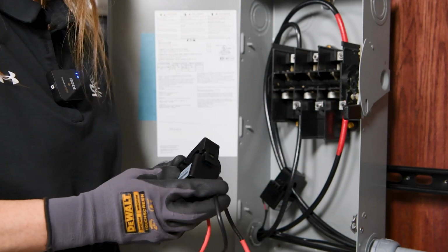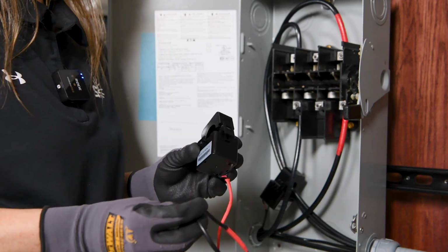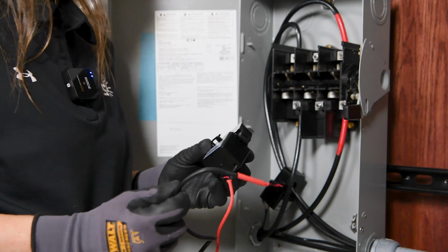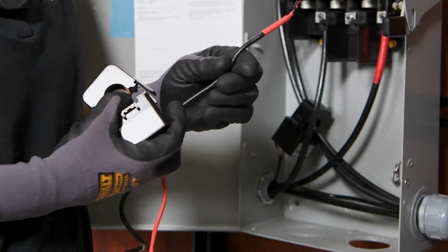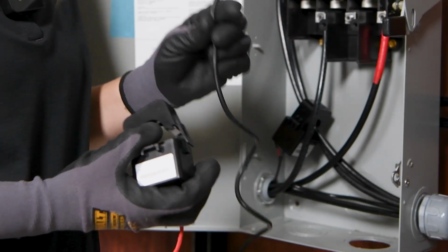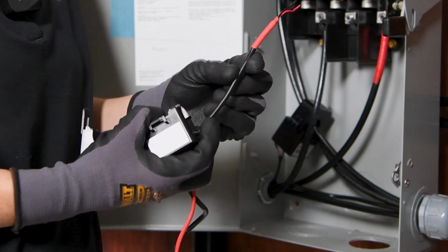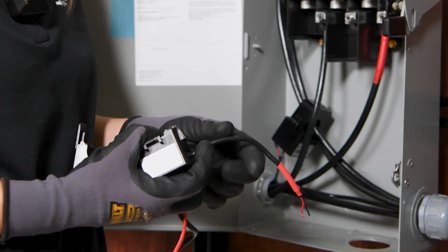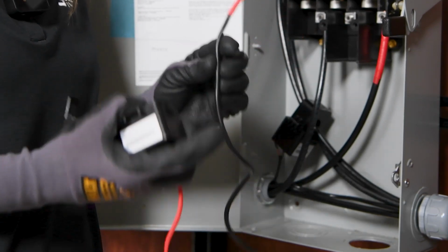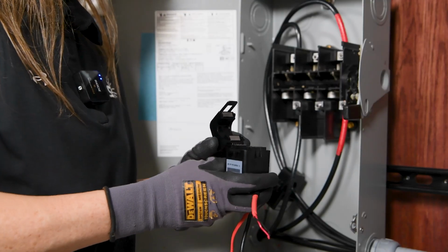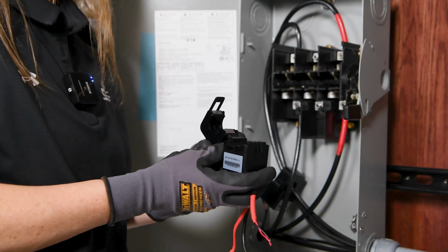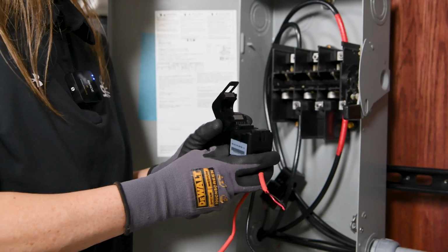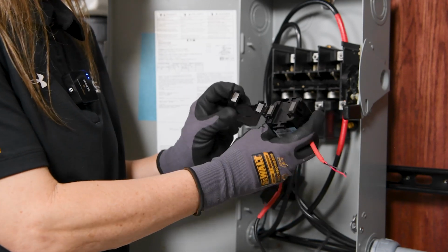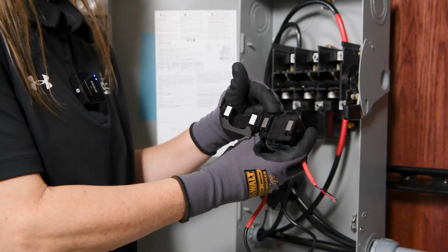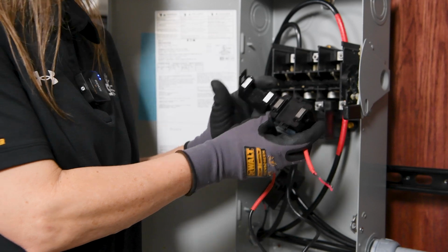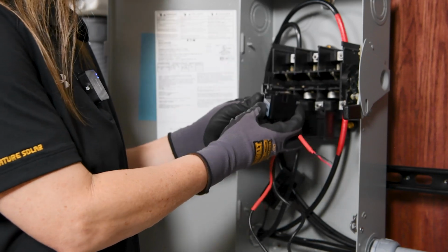And these will be required for self-consumption or export control for your load management. It is important that you are familiar with where you are applying these with your line 1 and line 2. We'll have to keep that consistent across all of our installation. These need to be installed between your meter and your main panel on your line 1 and your line 2. If you'll notice when you open these up, they have an arrow.